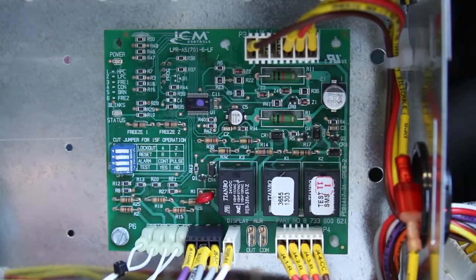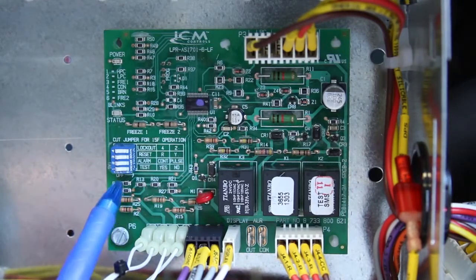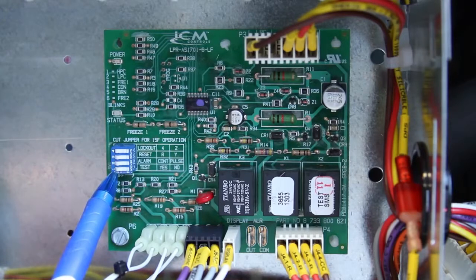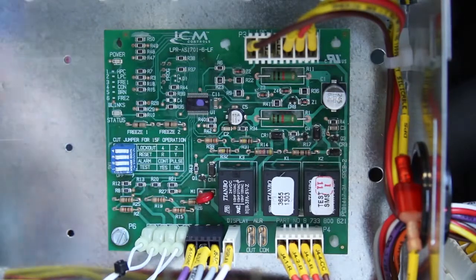Dip switch number 4, labeled test, comes in the no position. If you move it to the yes position and recycle power, it will shorten all of the time delays to 10 seconds so that you can diagnose problems without having to wait on the time delays to expire. For a complete list of all of the functions of the UPM board and all of the options available for connecting to your controls, please consult the installation and maintenance manual.